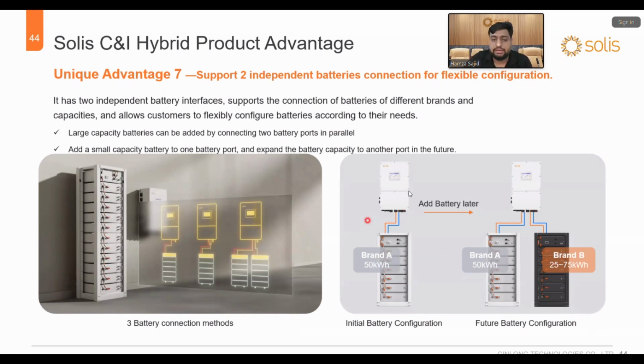So he found Brand A and installed that. After 1 year or 2 years, he comes to know that he needs to install more batteries with the system. He could not find brand A, or he finds brand B to be more easily available in the market. In that case, he can install two different battery brands at the same time with the inverter, because the inverter supports two different inputs for the batteries and two different BMS compatibilities. So you can attach two different brands to the system.